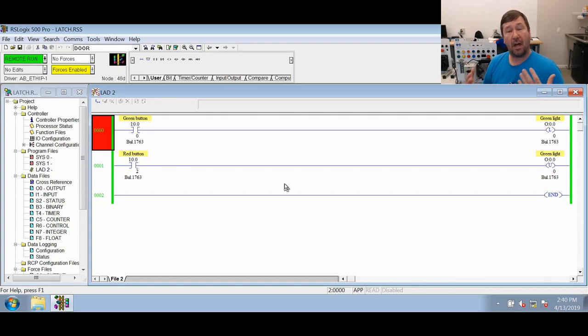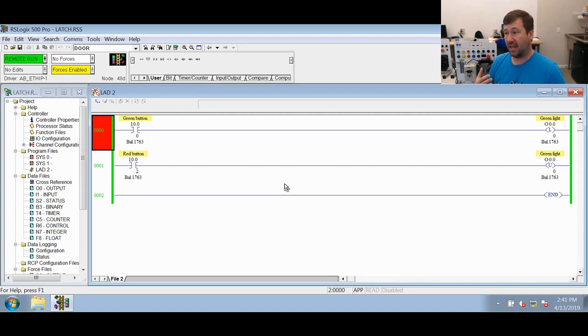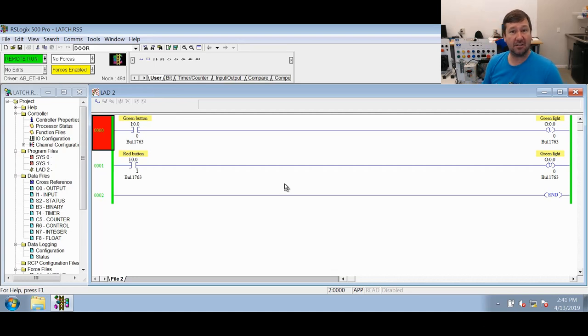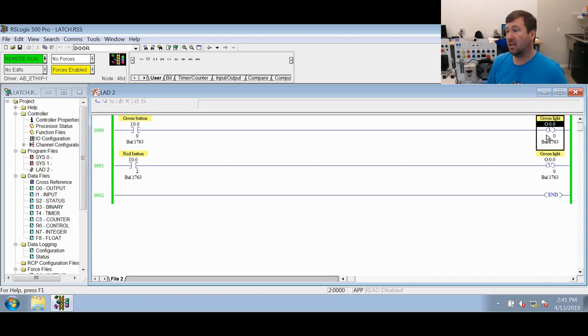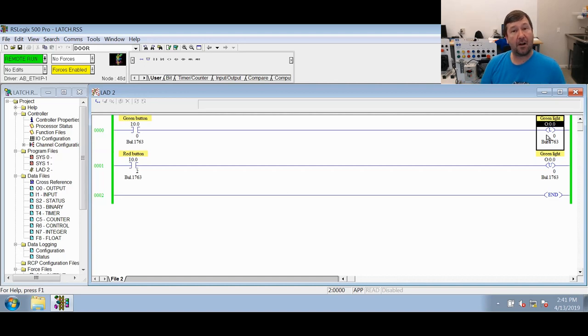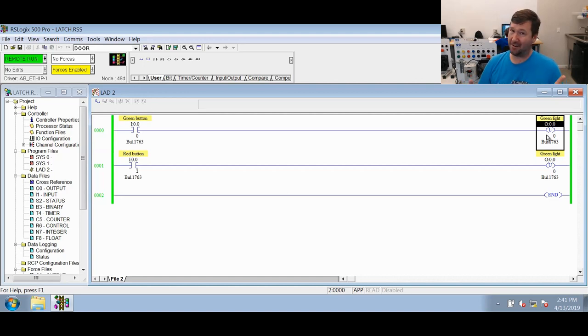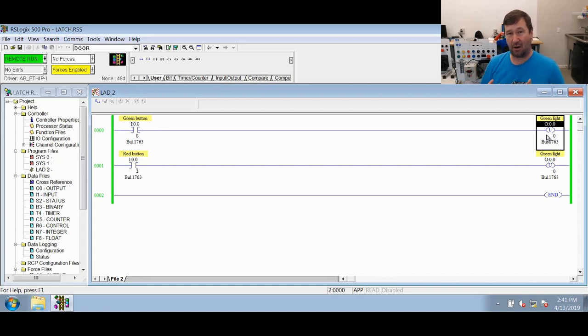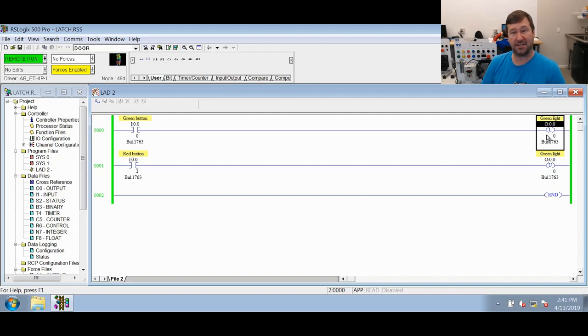The OTL and OTU output latch and output unlatch are simply an OTE instruction cut in half. So a true OTL instruction says go write a one, and a false OTL instruction does nothing. That's right. As much as I told you that false instructions always do something, this is one of those exceptions.